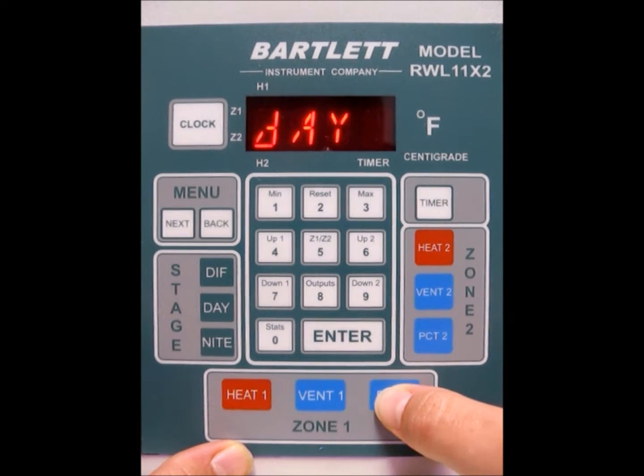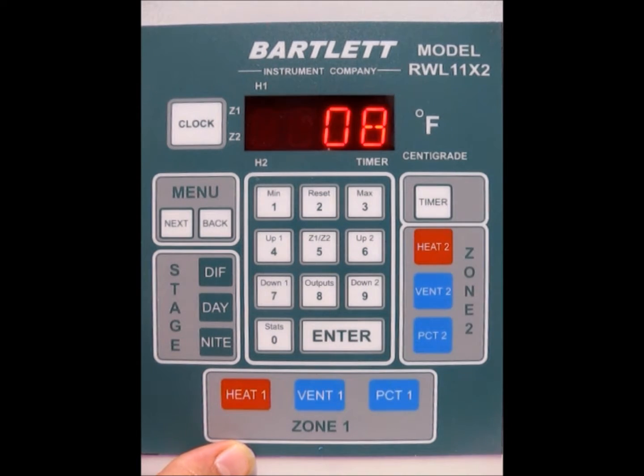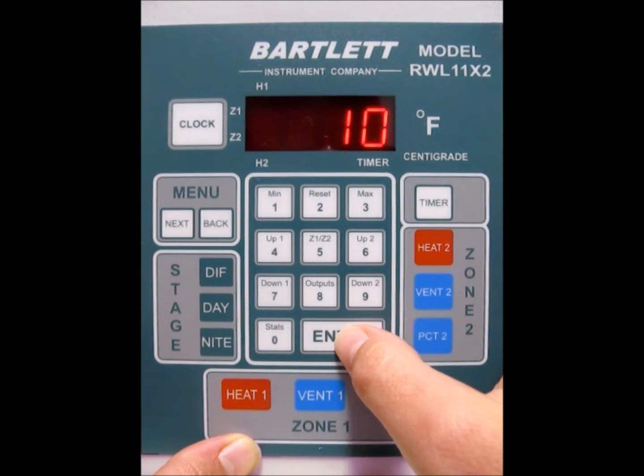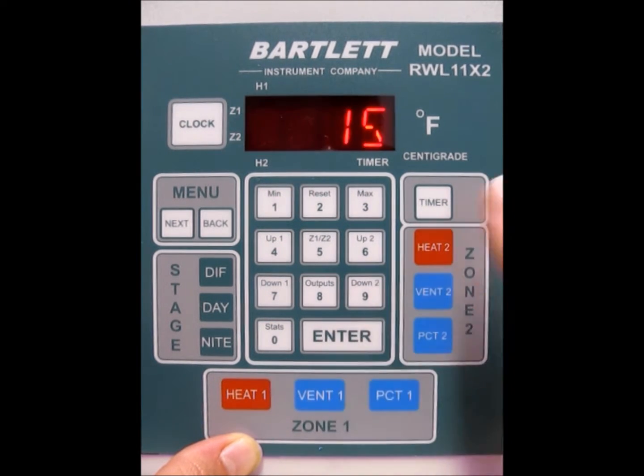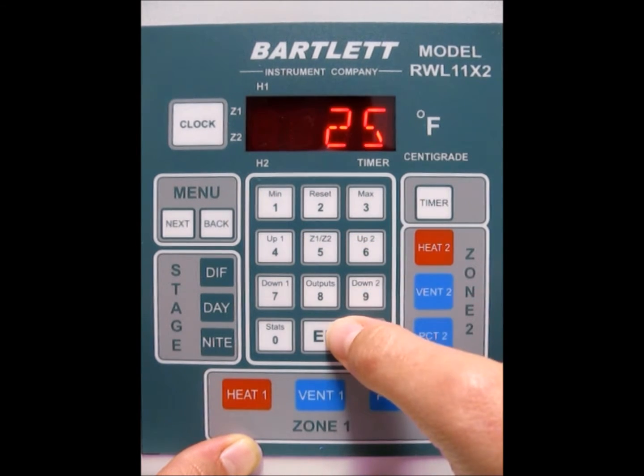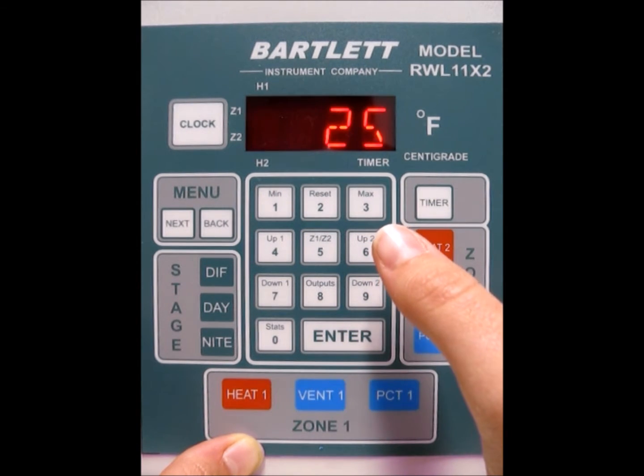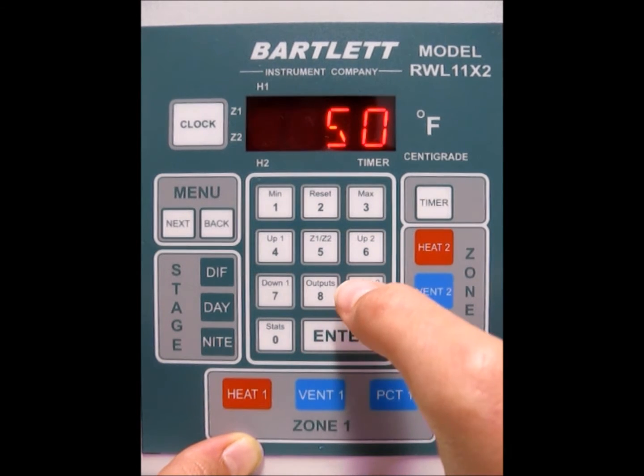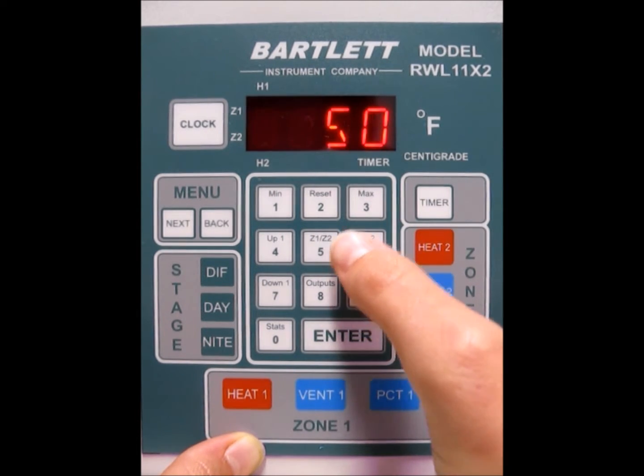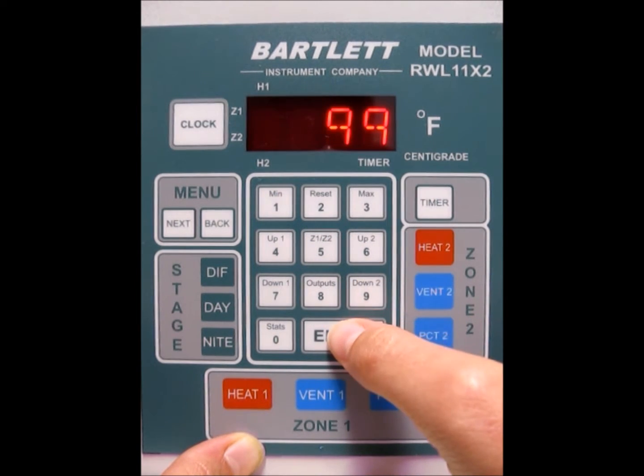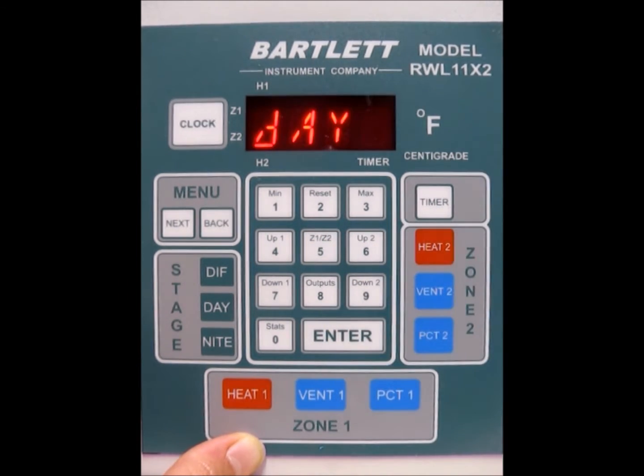Now program the percentages for vent 1. Press the PCT1 button. For percent 1, put in 10 and press enter. PCT2, go with 25. PCT3, go ahead and do 50. Number 4, we're going to do 75. And the last one we'll leave at 99, so just press the enter button. Now we're back at the idle screen.